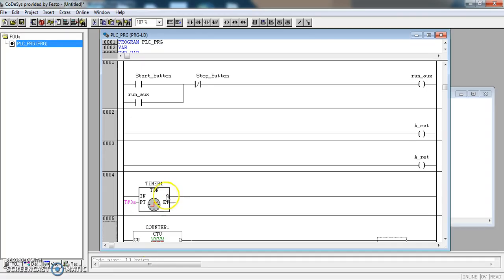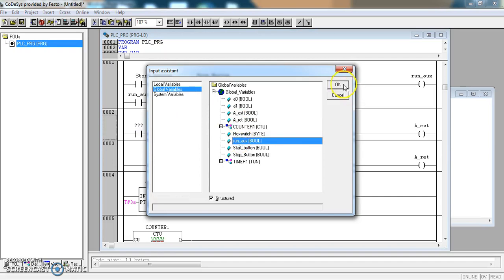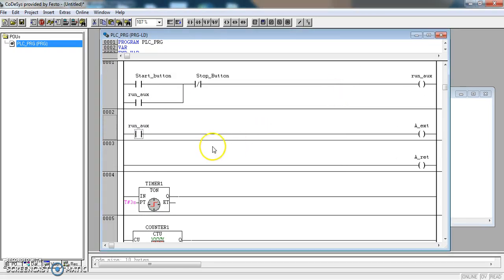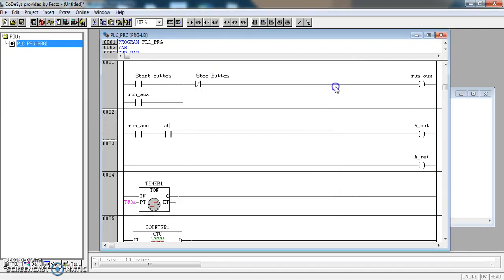So I'll write that piece of program in. If the start button is pressed that will turn on our run auxiliary, so we will use a normally open contact from the run auxiliary along with a normally open contact from roller switch A0, because those are the two requirements for A to extend.